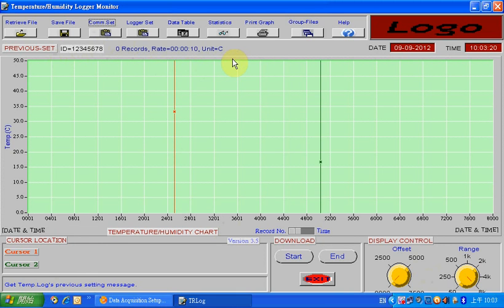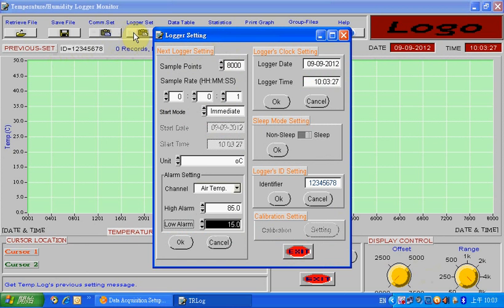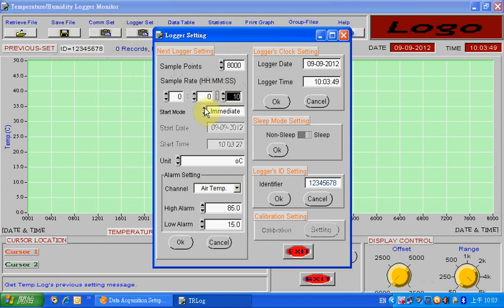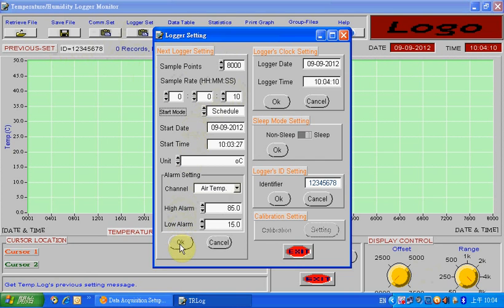Next, you can start setting your logger. Click Logger Set from the start menu. In this box, you can set the sampling rate — this means what interval you want to record the data. You can also set the start mode: immediate start, schedule start, or key start. If you choose schedule start, you need to further set the start date and time. You can also set high-low alarm values if needed. After the setting, click OK to complete the logger setup.